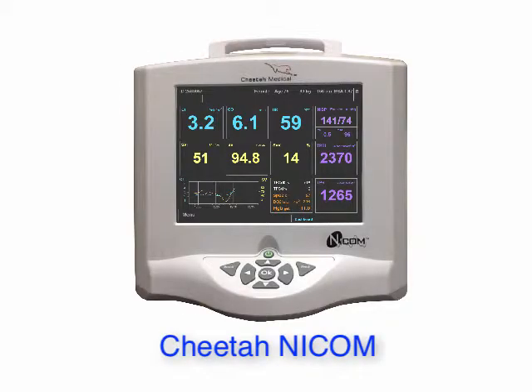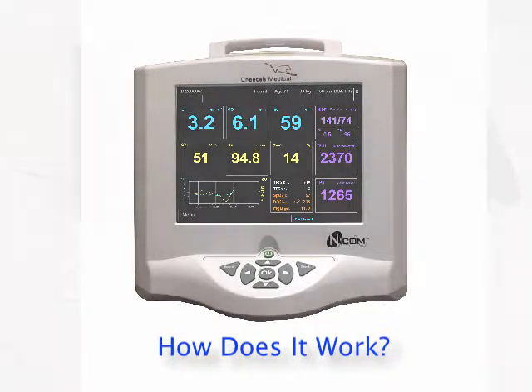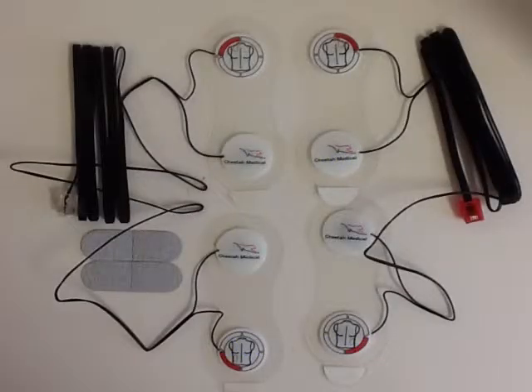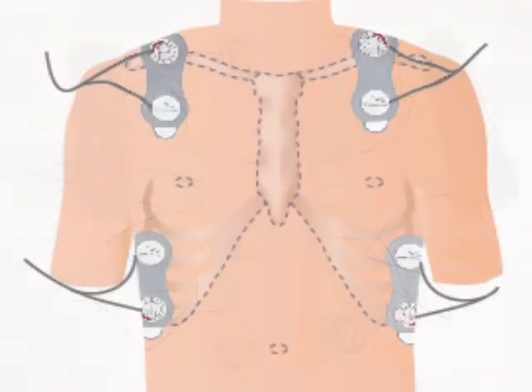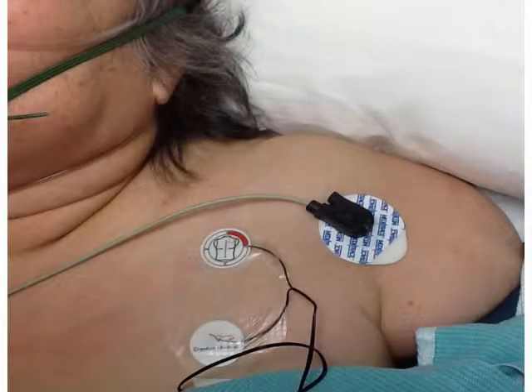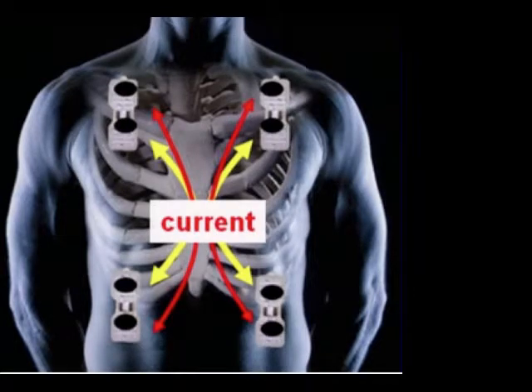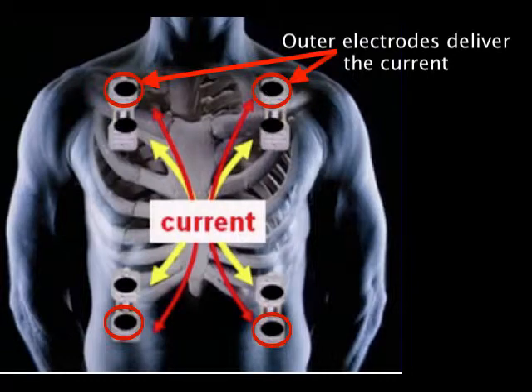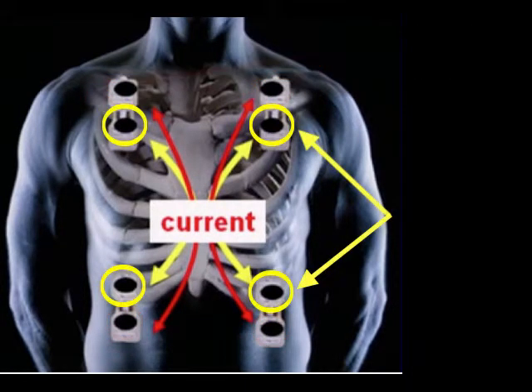This video provides an overview of how the Cheetah Non-Invasive Cardiac Output Monitor, or NICOM, obtains its data. NICOM uses 4 sensors applied to the right and left sides of the chest to create a thoracic box. Each sensor has a double electrode configuration consisting of an outer transmitting electrode and an inner receiving electrode. A low amplitude AC current with a frequency of 75 kHz is applied to the thorax from the outer electrodes. The inner electrodes measure the returning voltage.